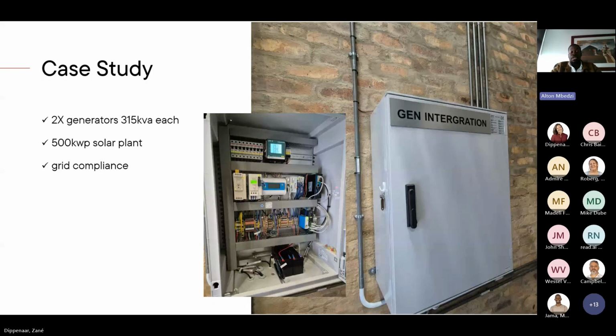This is the first cabinet where we were able to manage two generators with a 500 kilowatt peak solar plant, where we also did grid compliance. All of this was mixed together to make sure the plant was grid compliant, and to make sure the safety of the generators, each generator's output power, not just the total summation, is met so that we don't damage the generators over time.